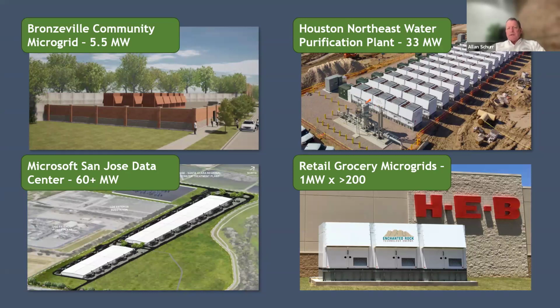This is a water pumping plant in Houston, Texas. The city of Houston is our customer—they move a significant amount of surface water around the Houston metropolitan area as a supplier to many other municipal utility districts, and they need to back up these pumping stations against a potential grid outage, either locally or at the system level. This is a 33 megawatt microgrid, and I use this picture first because it shows the construction approach we take. There are 75 separate generators at this site, each a standalone unit not electrically connected to any of the others, which allows them to operate at a very high reliability level.